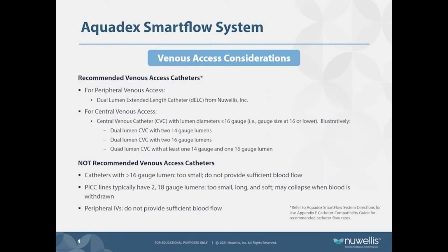Venous access considerations. The following are the recommended venous access catheters for use with the Aquadex SmartFlow system. For peripheral venous access, the dual lumen extended length catheter or dELC, and for central venous access, a central venous catheter with lumen diameters less than or equal to 16 gauge, in other words, a gauge size of 16 or lower. Illustratively, a dual lumen CVC with two 14 gauge lumens, a dual lumen CVC with two 16 gauge lumens, or a quad lumen CVC with at least one 14 gauge and one 16 gauge lumen.